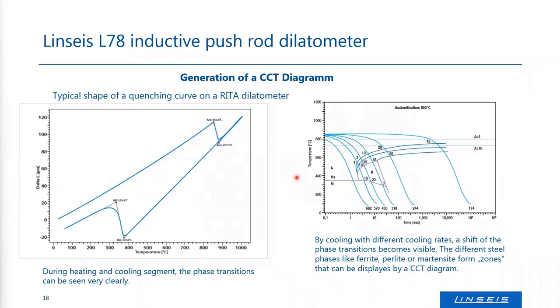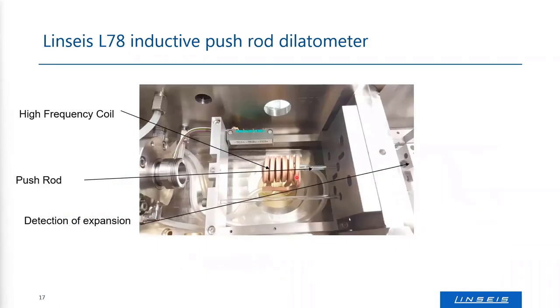For some applications, cooling down with maximum cooling rates is necessary. The highest possible cooling rates can be achieved by purging a cooling gas through small holes in the copper coil directly onto the sample to quench it. Usually helium or nitrogen gas is used, but if the highest possible cooling rates are needed, hydrogen gas is used. So this is also a special application for hydrogen atmospheres.